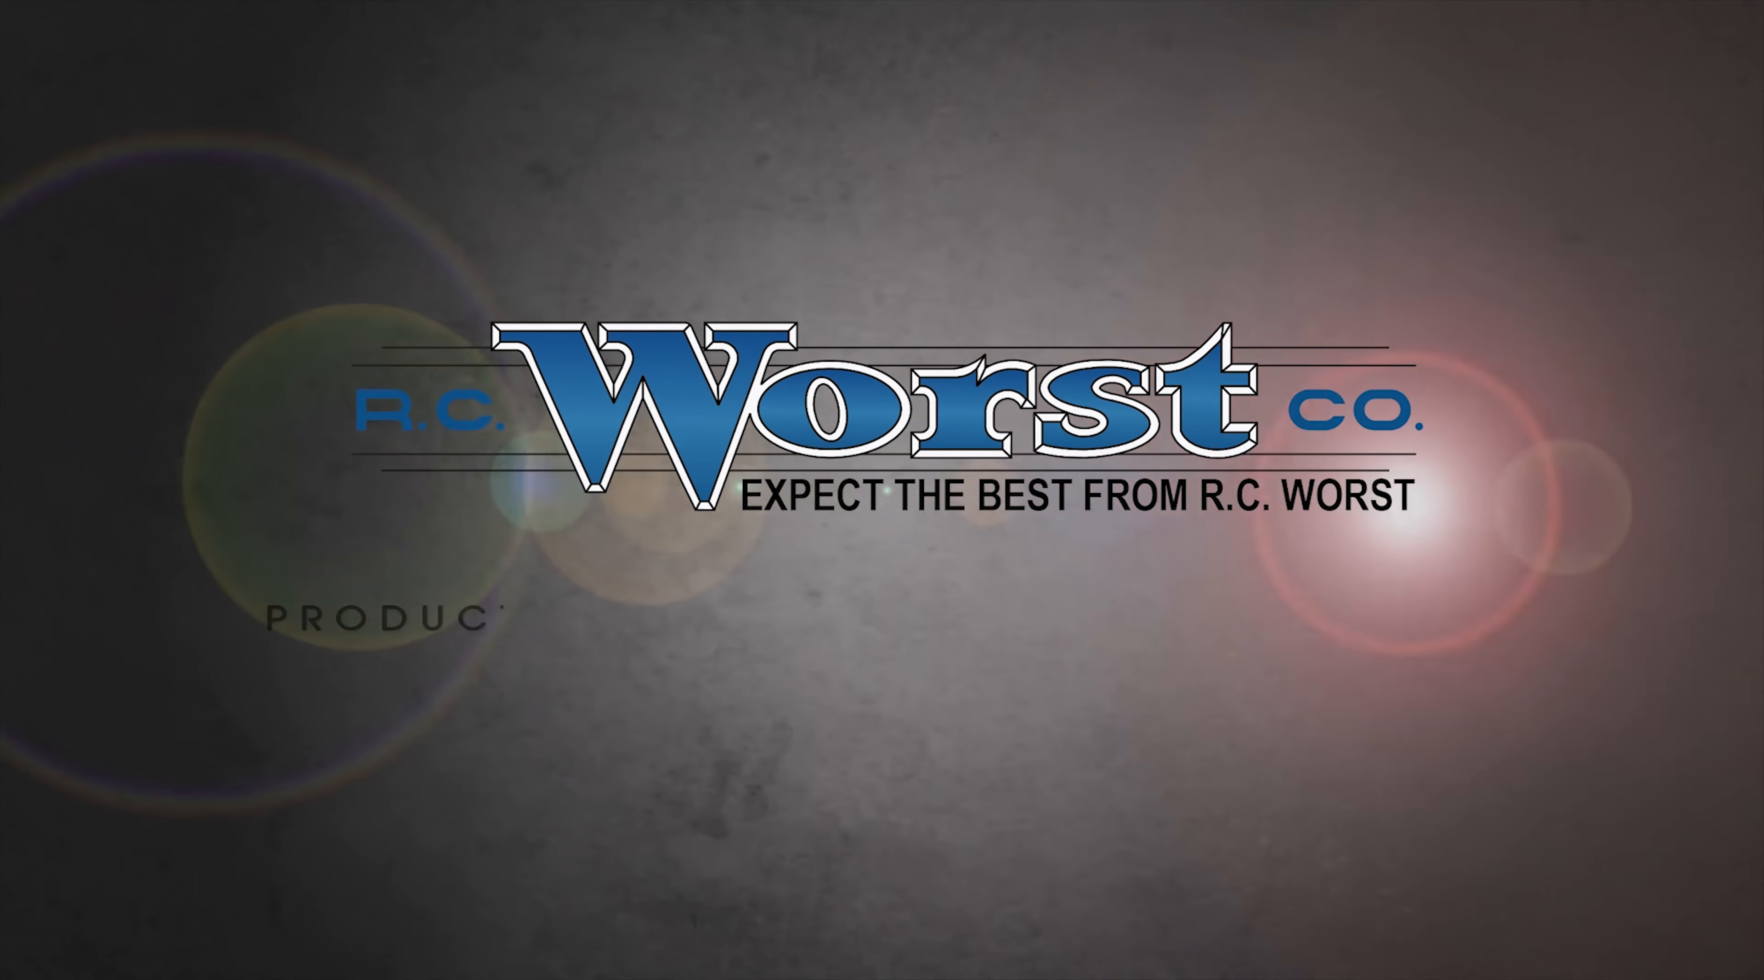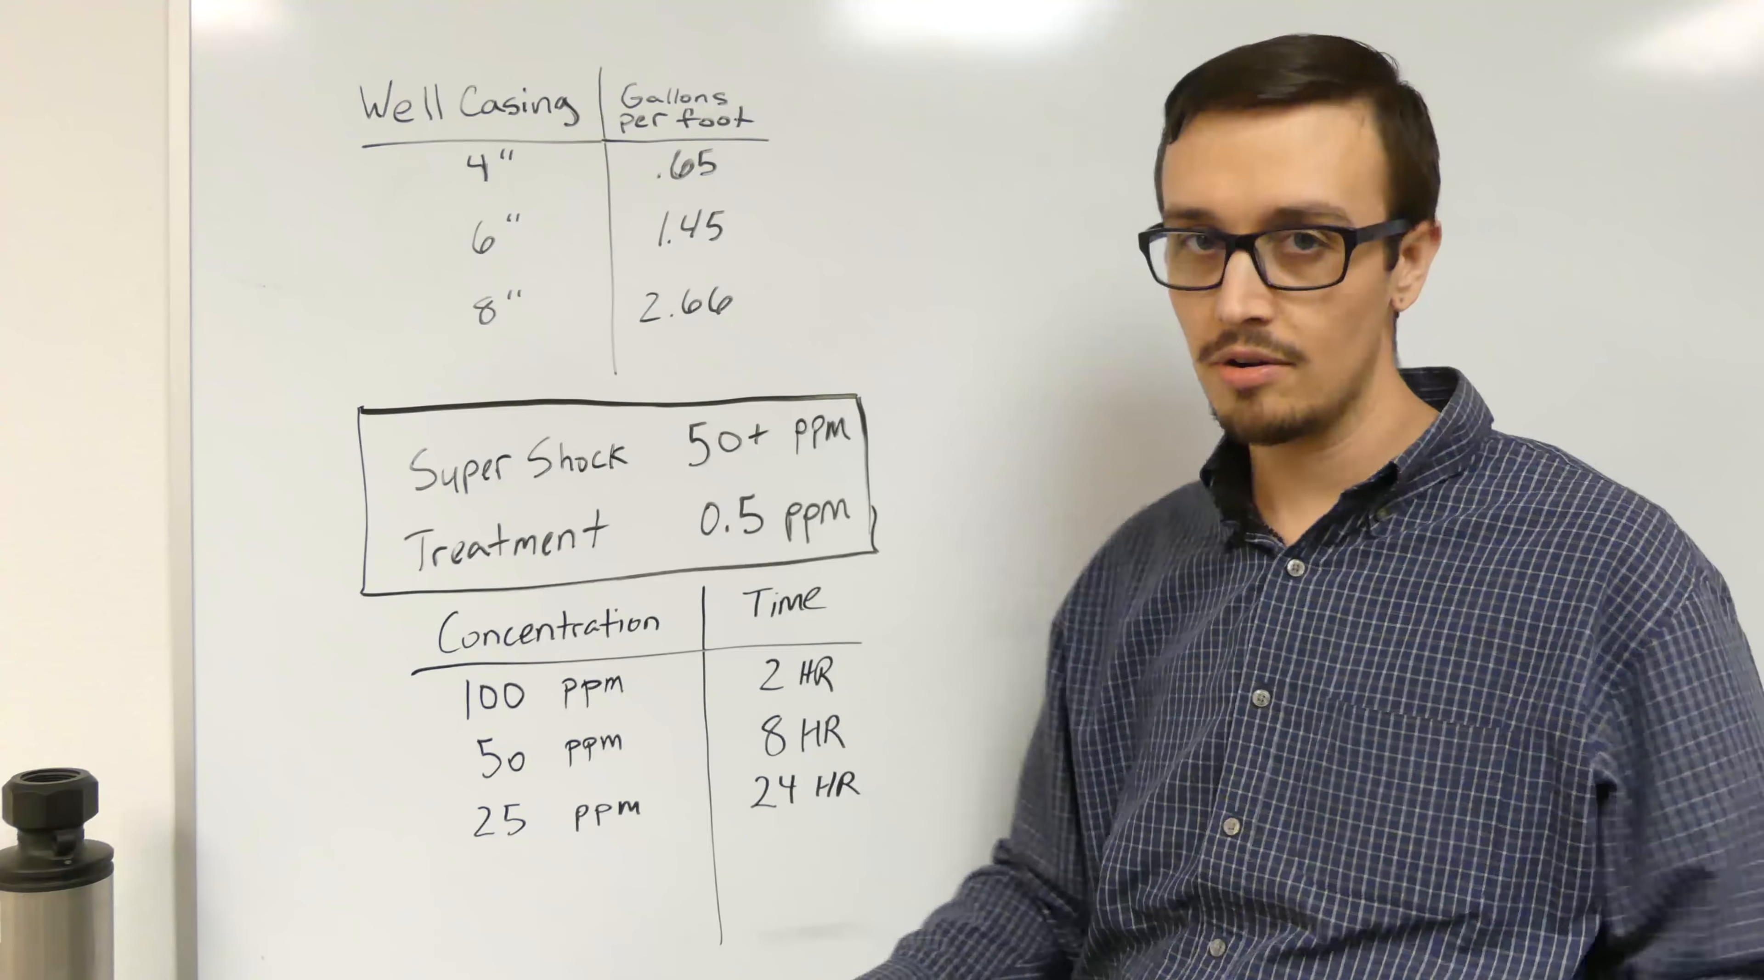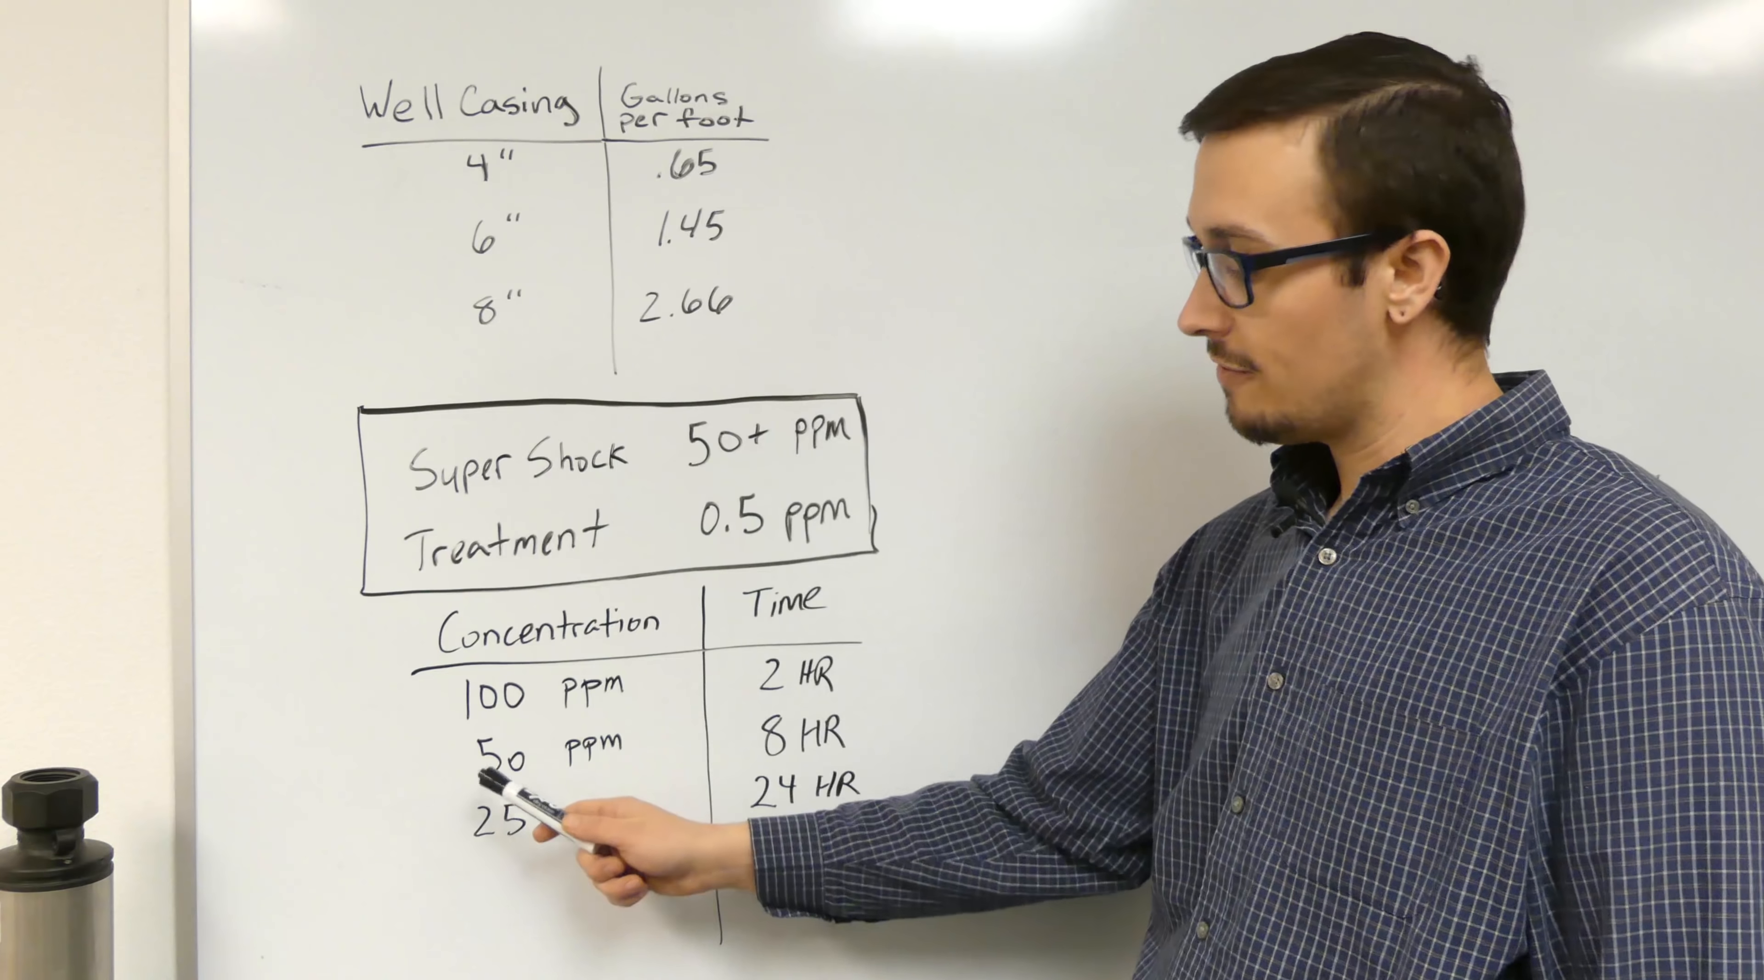A super shock or superchlorination or well shock, I've heard it called all kinds of different names, is typically 50 parts per million or more. It's quite a high concentration. Just to put that into perspective, most treatment like chlorination in the main city water line, the concentration is usually at or below a half a part per million, which is the tolerable drinking level.